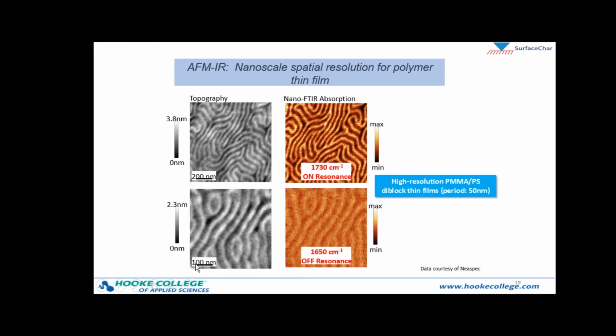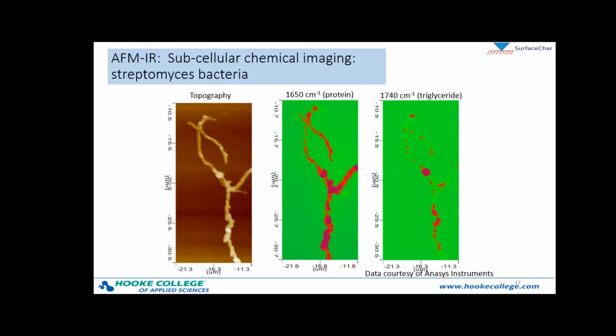And then here, even higher resolution. So here, this length here is only 200 nanometers. Here it's 100 nanometers. And you can see here they tuned off of the absorption peak and see very little contrast, showing that this is real, this contrast seen at 1730 wave numbers. So having this AFM platform to make these IR measurements and to build this IR information on top, on a very high resolution, less than 100 nanometers, on top of the nanoscale topography and mechanical property information from the AFM, again results in a very powerful tool to provide a very complete characterization from many different angles of the sample.